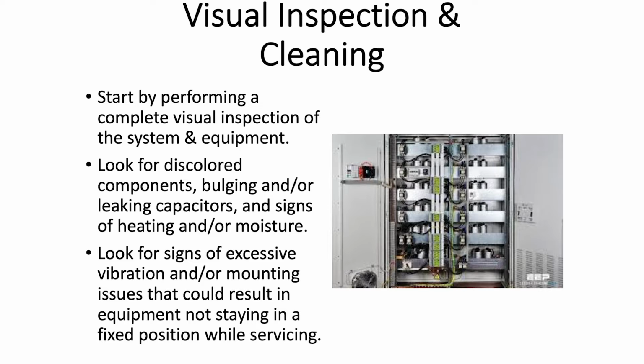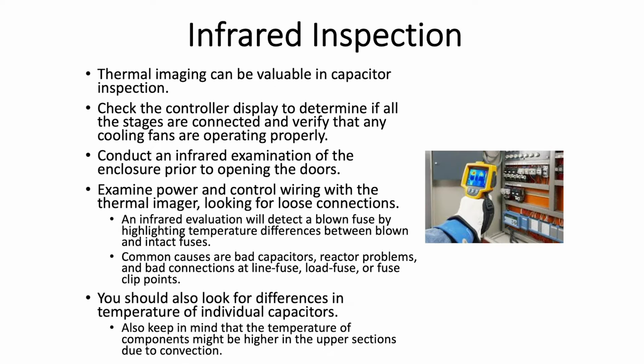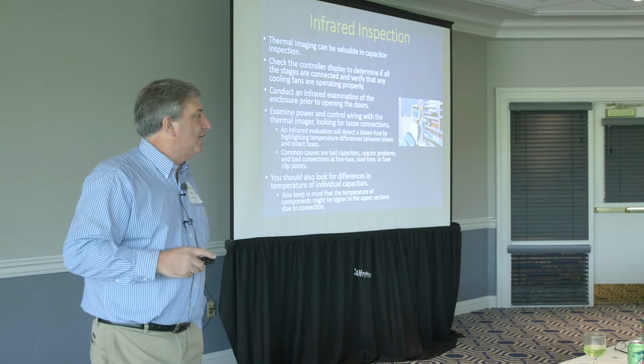Okay? Visual inspection. Look for bad equipment. If you open the door and the caps are laying down at the bottom of the panel, you probably know you've had some vibration and a mounting issue. Something like that. Look for those signs. Infrared inspection is starting to catch on for cap banks as well. Not so much necessarily to see bad connections, although it helps with the shorting circuit, but to now see which caps might be charged and which ones aren't. Because those charged caps will be higher or hotter than a discharged cap.